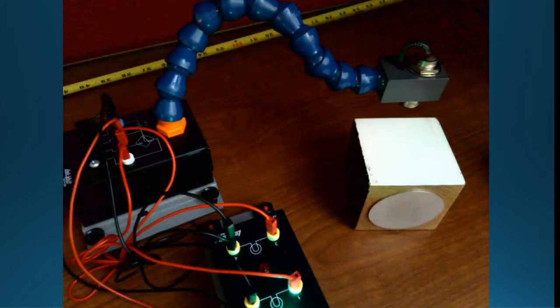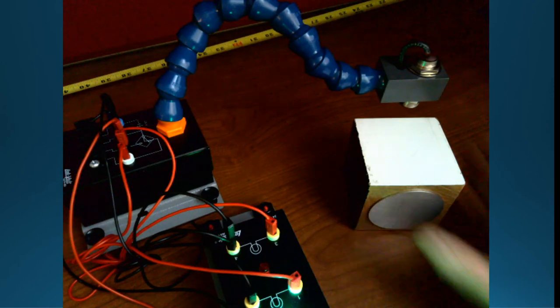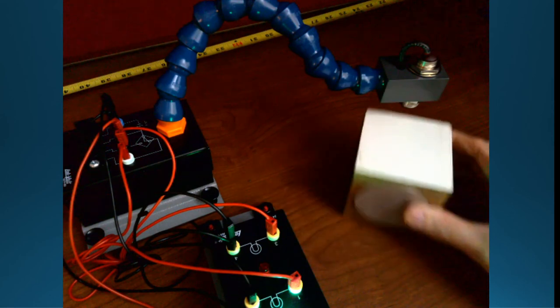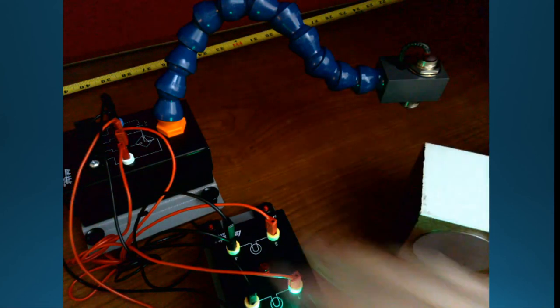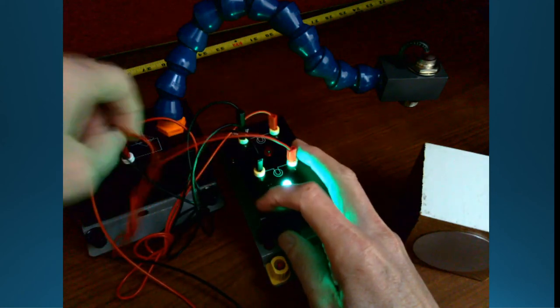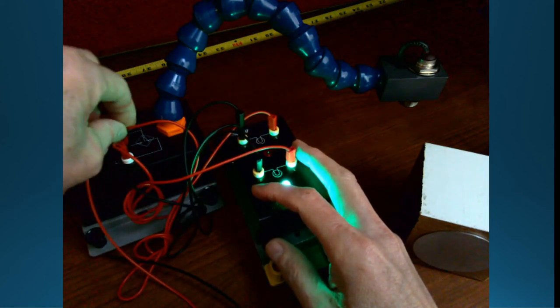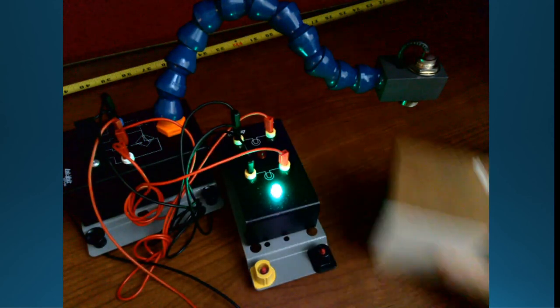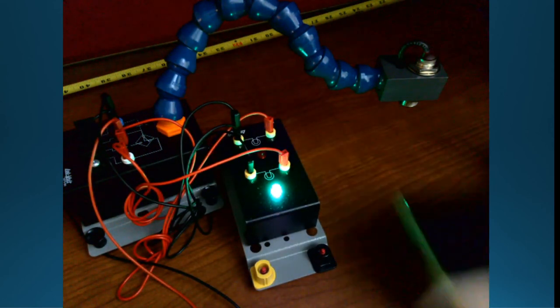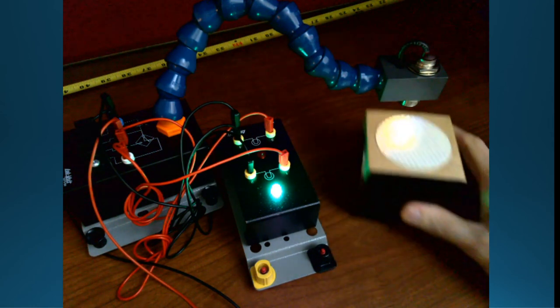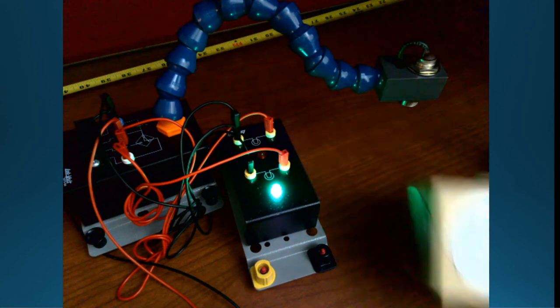With that, let's go through and look at the sensor. I'm going to go through and transition over here. So what I've got is the wooden block that we've been using so far. This is just white and you'll see that it doesn't trip it off. I've got it set up here. Green is my normally closed. There's the wood side, the black side. So the color reflection doesn't affect it. Here is that reflective end that doesn't trip it.